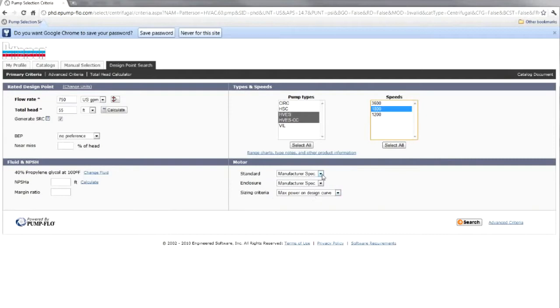Getting into the motors, do we want a standard motor? Well, I usually leave that to the manufacturer's specification. What kind of enclosure do we need? If we know we need something different, whether we want an open drip proof or a TEFC. Again, keep in mind that if it's an outdoor motor exposed to the outdoor elements, it better be the TEFC, or the totally enclosed fan-cooled motor. If it's inside, then it can be the ODP, or the open drip proof. So we'll leave that to the manufacturer's spec.